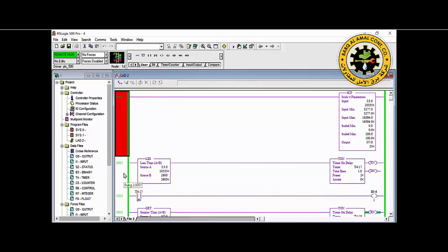And this is our first SCP command, which is the analog signal scaling. And the less-than comparison means 2.6 bar: when the pressure goes down below 2.6 bar, after this the pump will be started, and this PID value will continuously maintain the pressure at our set point. This set point is 5.5 bar, and the pressure will be maintained at 5.5 bar.